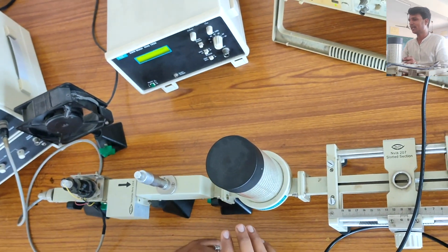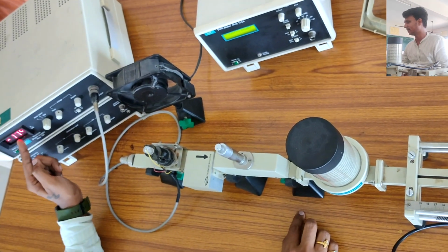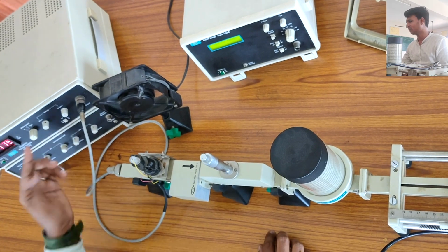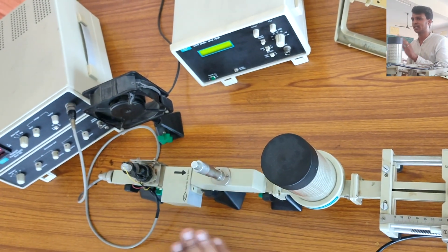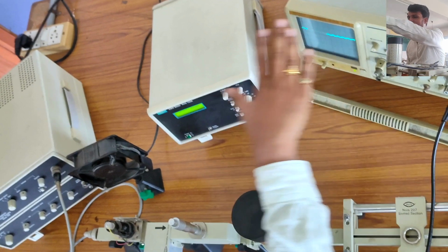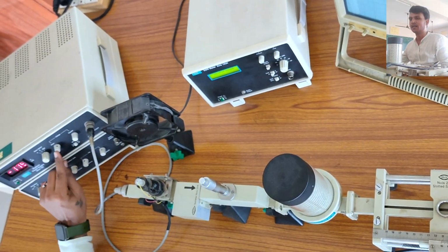So like that we have to set the beam voltage. First we set it at 210. Suppose for example if you want to set 215, that also we can do. The procedure is similar. We calculate the starting point and ending point with the help of the oscilloscope, and the power calculation for the starting point and ending point is also similar for each and every beam voltage setup.